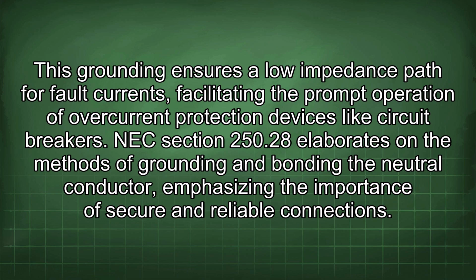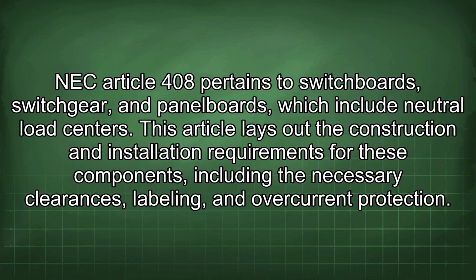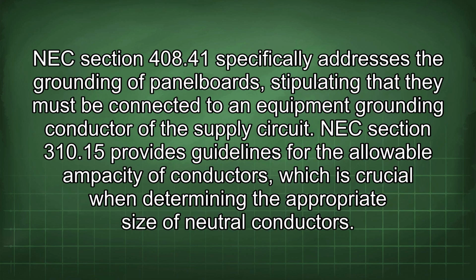and reliable connections. NEC Article 408 pertains to switchboards, switchgear, and panel boards, which include neutral load centers. This article lays out the construction and installation requirements for these components, including the necessary clearances, labeling, and overcurrent protection. NEC Section 408.41 specifically addresses the grounding of panel boards, stipulating that they must be connected to an equipment grounding conductor of the supply circuit.